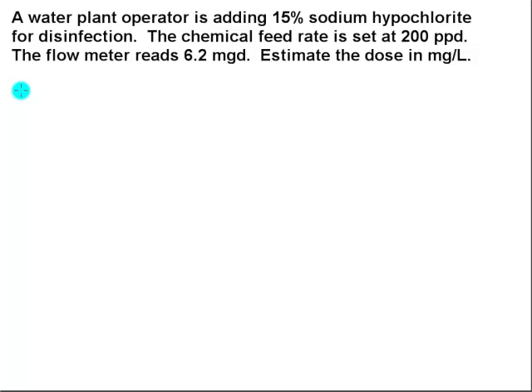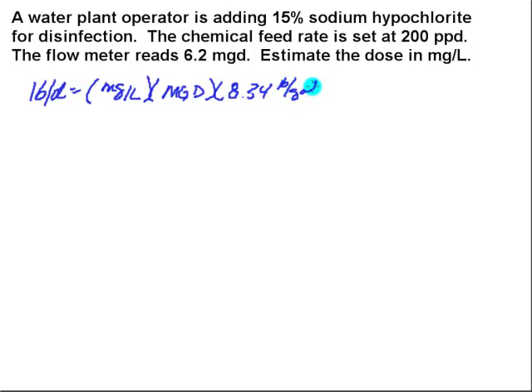Estimate the dose in milligrams per liter. Since I'm doing a chemical feed rate problem, I know that I need my pounds per day formula. Pounds per day equals the milligrams per liter of dose times the flow rate in million gallons per day times 8.34 pounds per gallon, all of that divided by the percent available chlorine.